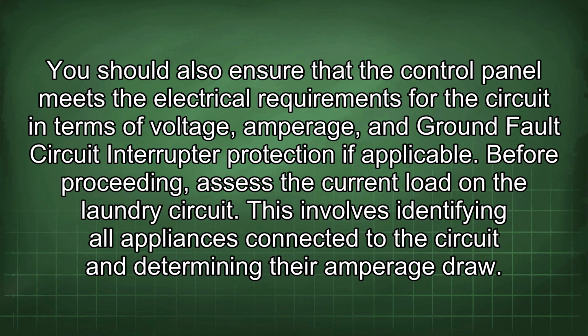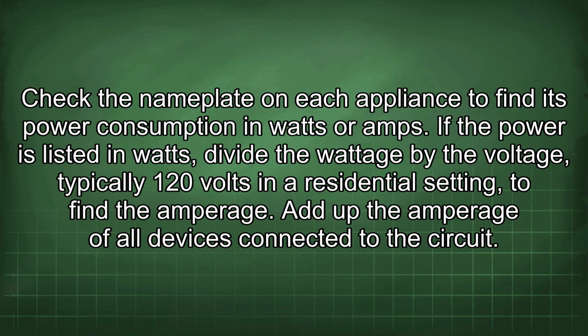Before proceeding, assess the current load in the laundry circuit. This involves identifying all appliances connected to the circuit and determining their amperage draw. Check the nameplate on each appliance to find its power consumption in watts or amps. If the power is listed in watts, divide the wattage by the voltage, typically 120 volts in a residential setting, to find the amperage. Add up the amperage of all devices connected to the circuit.